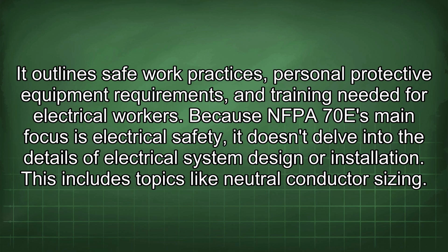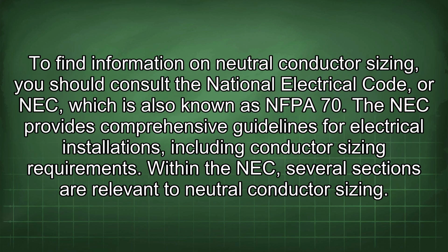Because NFPA 70E's main focus is electrical safety, it doesn't delve into the details of electrical system design or installation. This includes topics like neutral conductor sizing. To find information on neutral conductor sizing, you should consult the National Electrical Code, or NEC, which is also known as NFPA 70. The NEC provides comprehensive guidelines for electrical installations, including conductor sizing requirements.